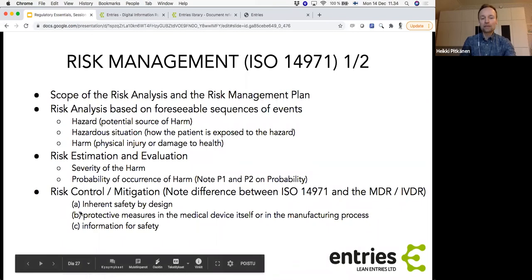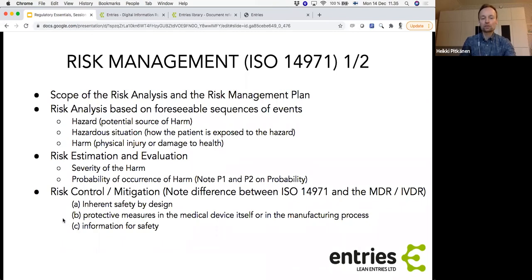And then the last resort, so to speak, is information for safety. So you put that information into an instructions for use as contraindications, for example, and then you need to rely that the people read this IFU. And if you are not sure that they will read them, it might be necessary to provide them any training on your device. That will also fall in the category C of information for safety, to make sure that they use the device according to your specifications and intended purpose. And again, a lot to do with your business. If they are not capable of using your product correctly, it is your business that is on the line.